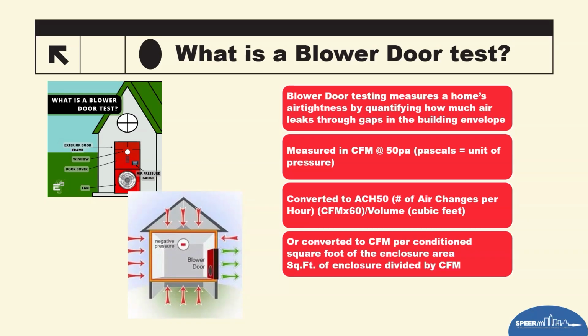They're 800 square feet. They don't have a garage. They're not an encapsulated home. They don't have a lot of volume. So to get to a very tight 5 ACH, or a 4 or a 3, is nearly impossible if you just don't have the volume of air to do the calculation to get there. So they came up with that CFM per square foot of conditioned enclosure surface. This allows tight buildings to have a higher ACH but still be compliant with the code.